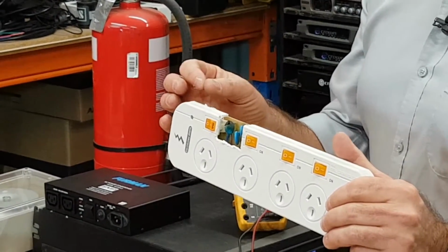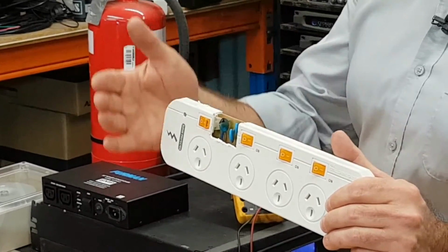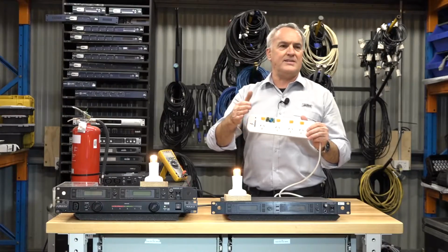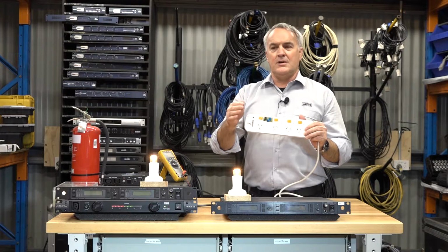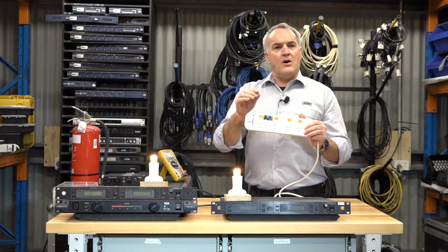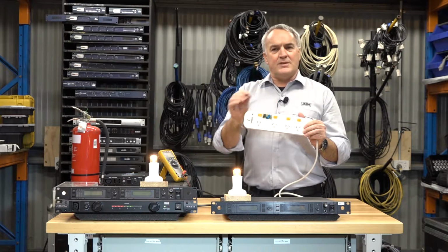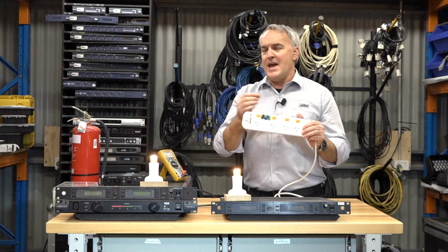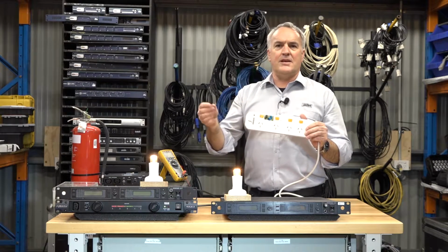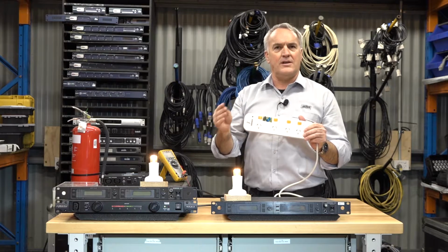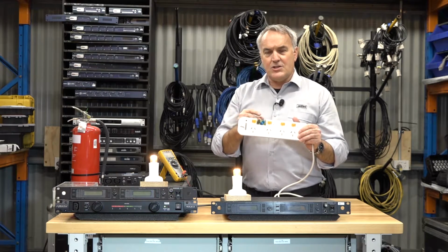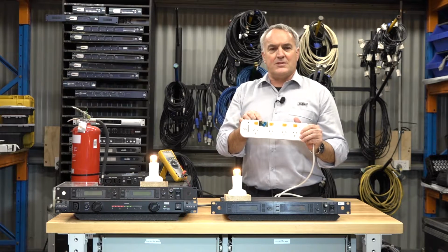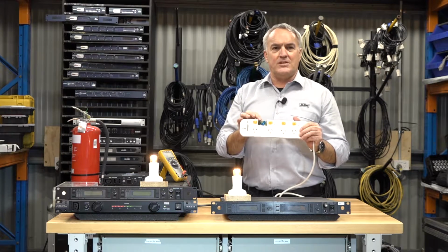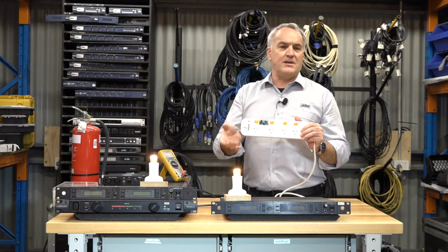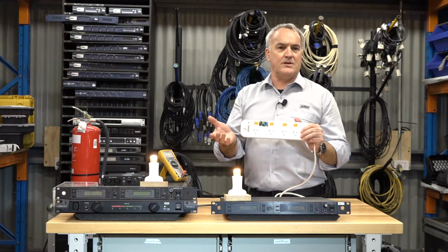The problem with this approach, though, is that the MOV and your connected equipment are always in parallel online. So you're relying on the MOV shunting as much energy away as it can, but it can't disconnect your product. It's always still online, it's always still going to be exposed to some degree. Additionally, the MOV itself will at some point, if it tries to absorb too much energy, explode. And then once it's out of circuit, it no longer protects your devices.